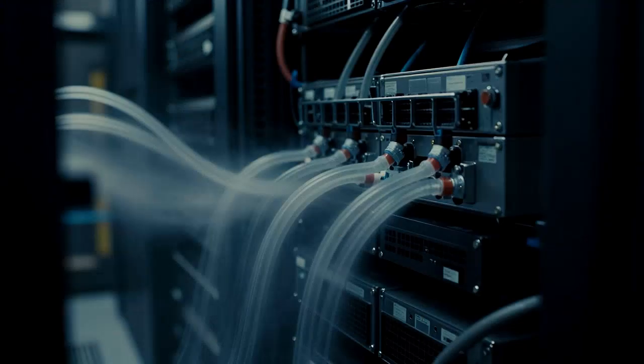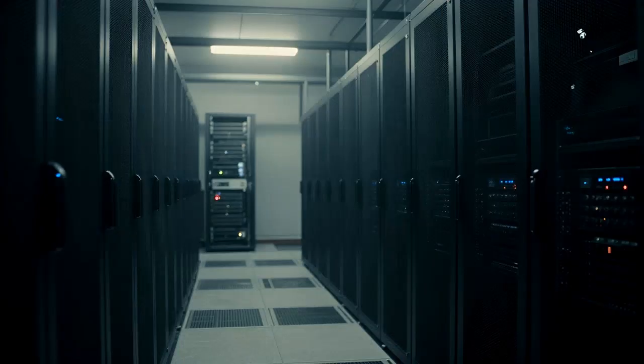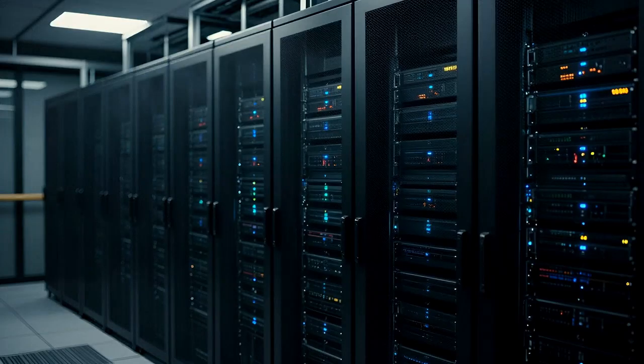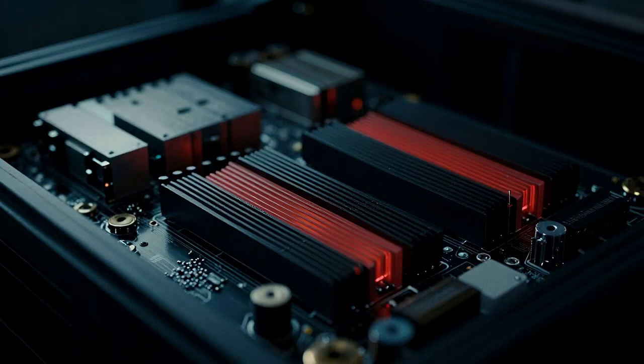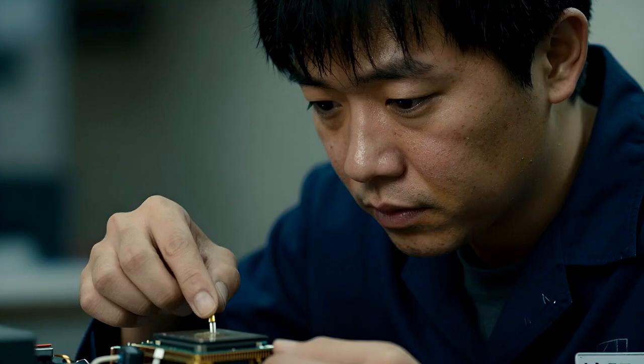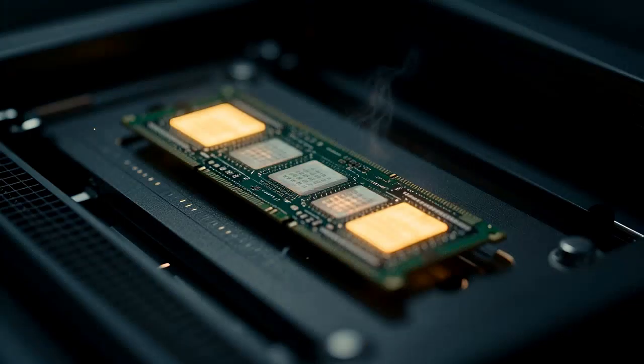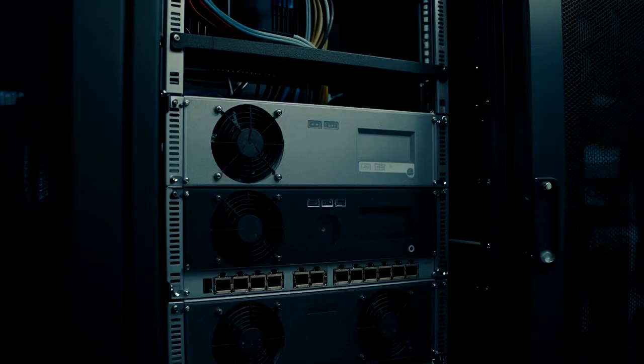A well-designed loop can capture and remove 70% to 80% of the total thermal load of a server rack right at the source. This massive reduction in cooling overhead enables facility power usage effectiveness ratios to drop from a stagnant, power-hungry industry average of 1.5 down to near-perfect scores of 1.1 or 1.2. However, there is a structural limitation. It is a targeted strike. It only cools the specific, flat components that the cold plates physically touch. The remaining 20% to 30% of the heat, generated by memory modules, optical network switches, and heavy power supplies, must still be managed by supplemental air cooling infrastructure.